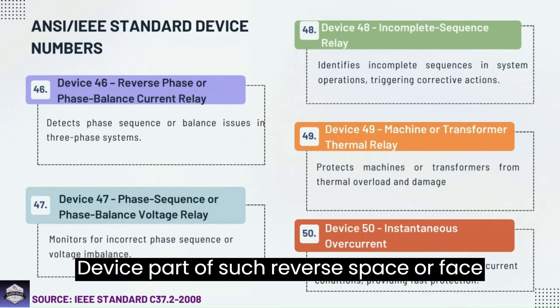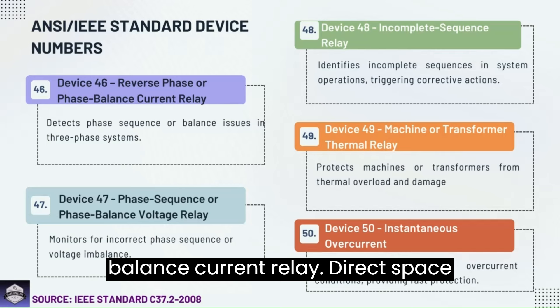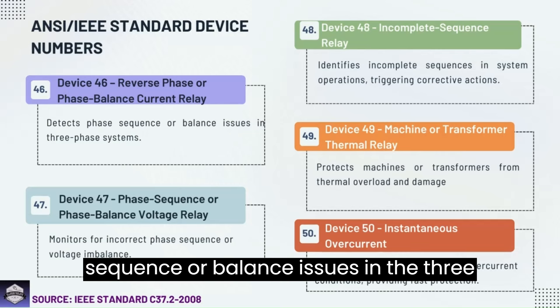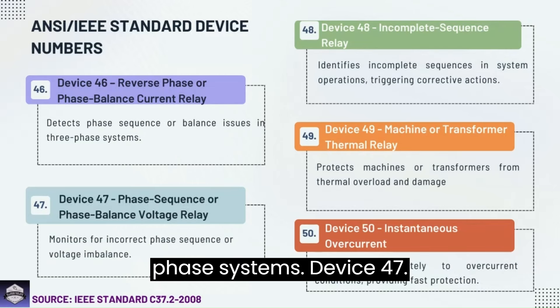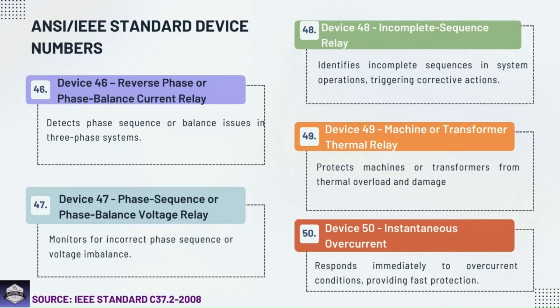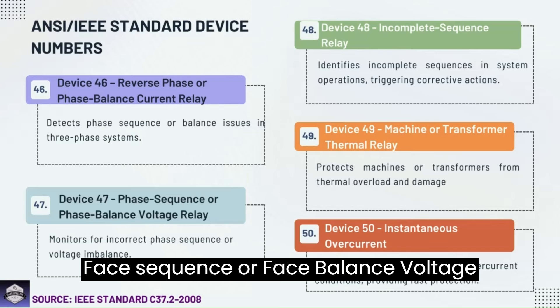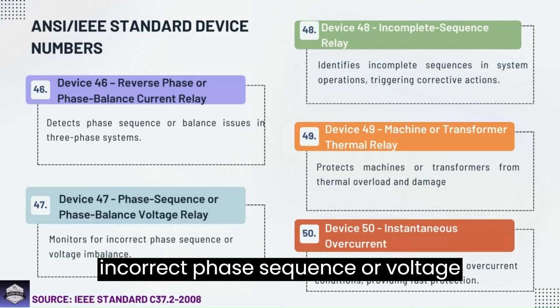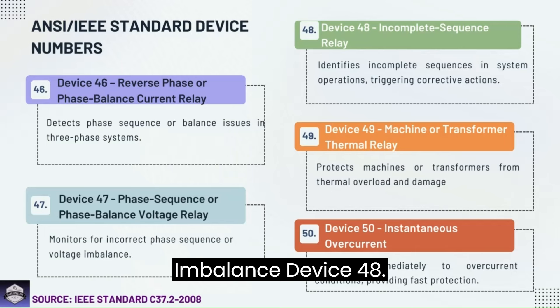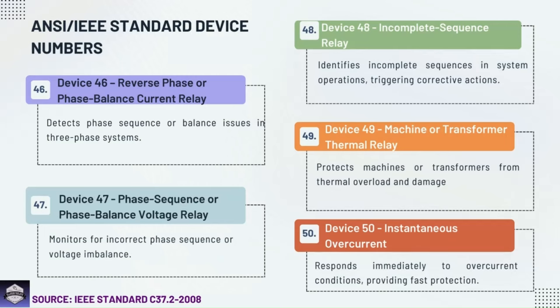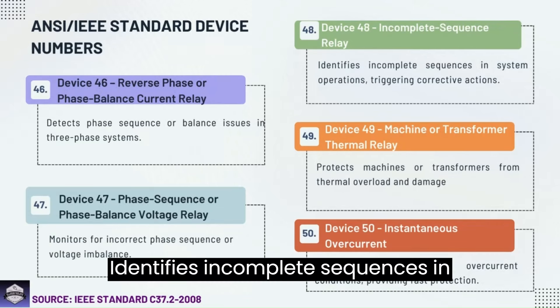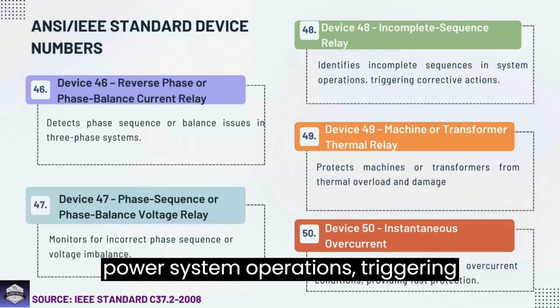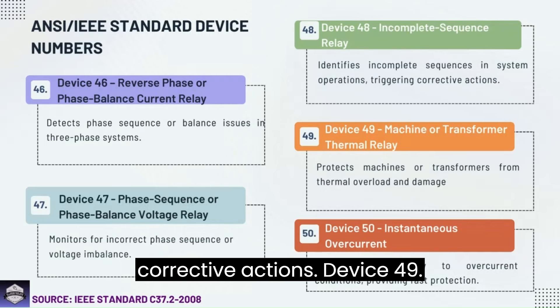Device 46: Reverse phase or phase balance current relay — detects phase sequence or balance issues in three-phase systems. Device 47: Phase sequence or phase balance voltage relay — monitors for incorrect phase sequence or voltage imbalance. Device 48: Incomplete sequence relay — identifies incomplete sequences in power system operations, triggering corrective actions.